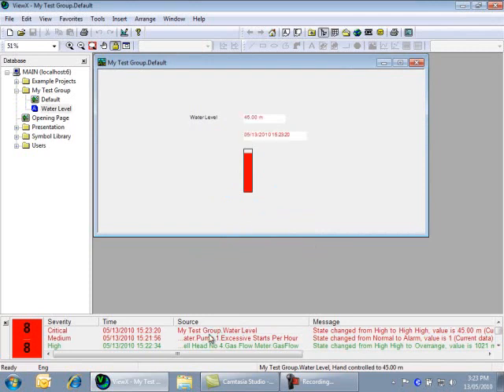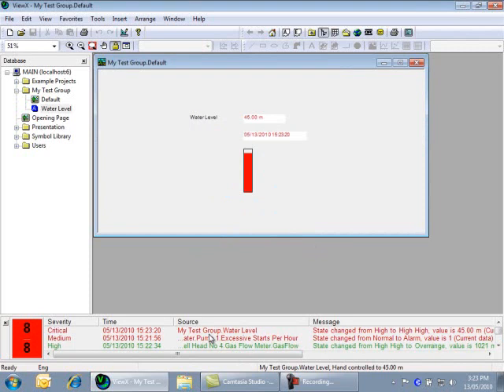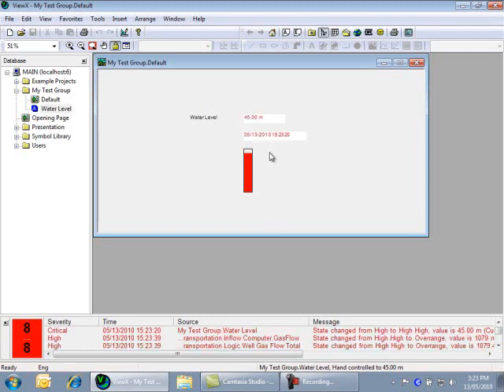An alarm now appears in the alarm banner. It shows it's flashing red because it's unacknowledged and uncleared. That means it's still active, and it has not been acknowledged by an operator. Notice also that the text for this point on the mimic uses the same color effects. This allows an operator to know the state of the point, no matter where they look at it in the system.